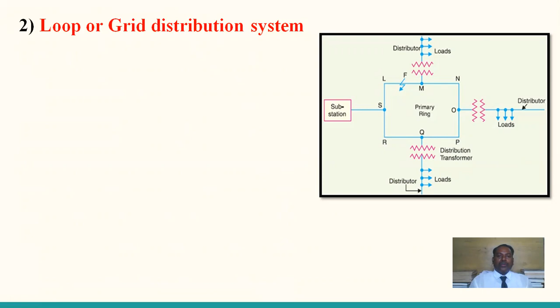It is selected to carry its normal load plus the load of the other half of the loop also. So in a mesh or loop, the conductor is selected such that it will carry its original load plus the load of the other half. Then only it can stand. Suppose one side has a problem, the entire current goes to this side, so it can carry double the load than existing. Therefore, the conductor is selected to carry its normal load plus the load of the other half of the loop path. Therefore, the size of the feeder conductor in a loop distributor is the same throughout the loop.